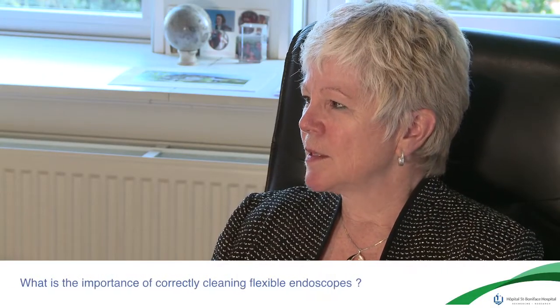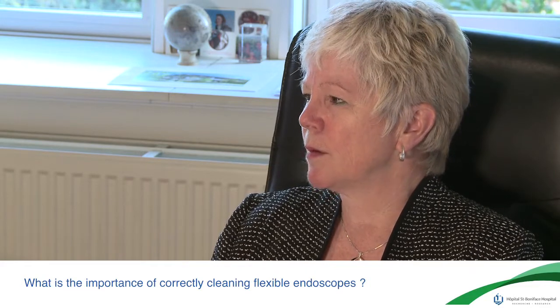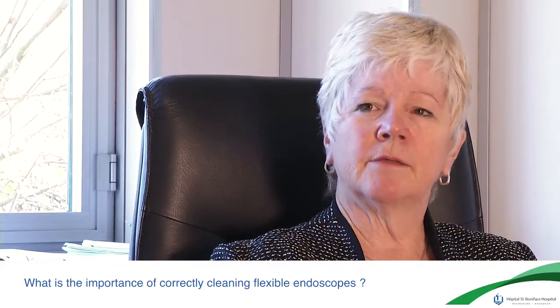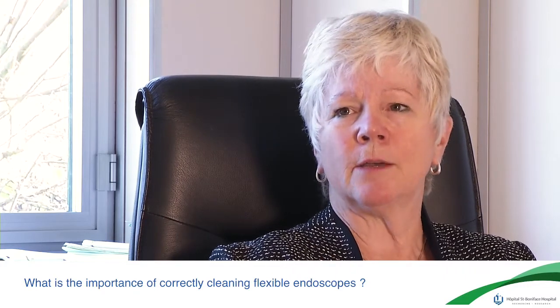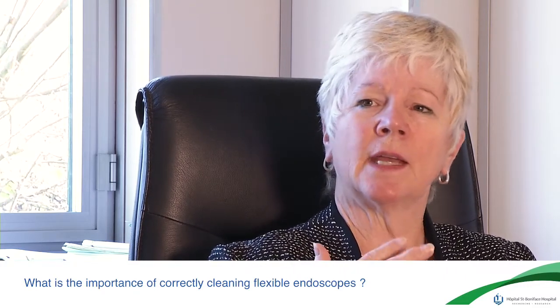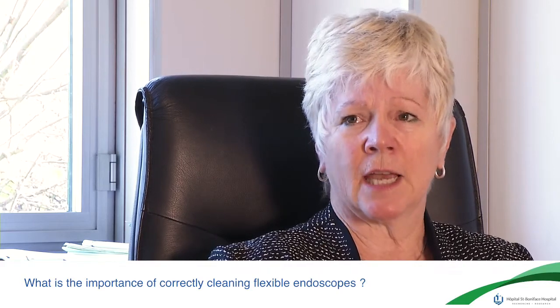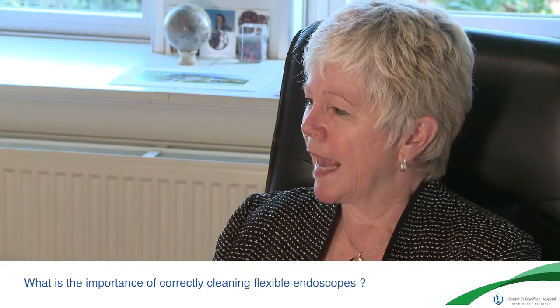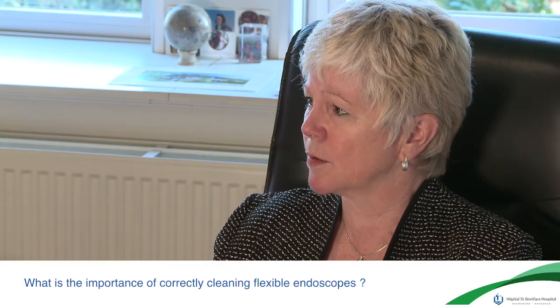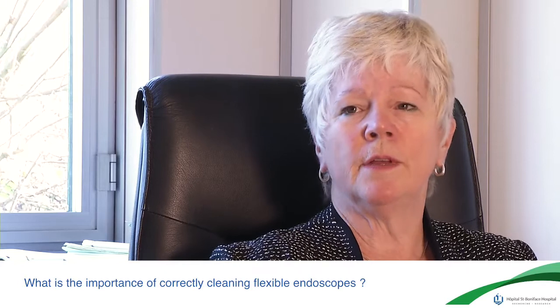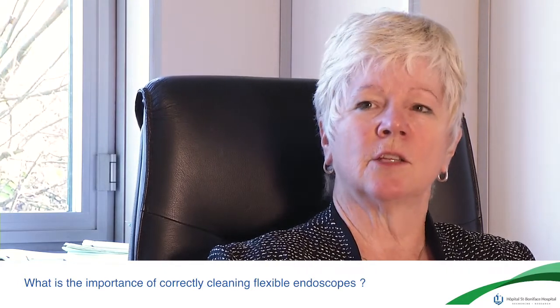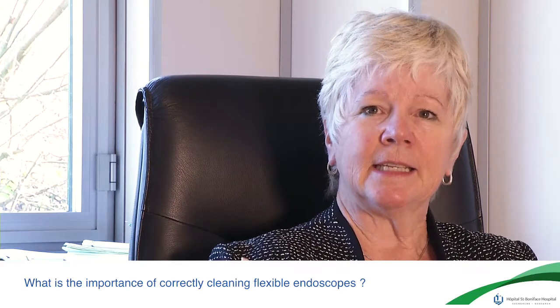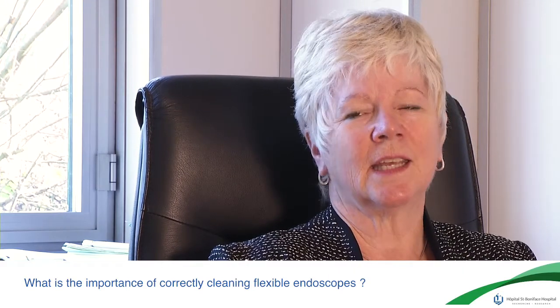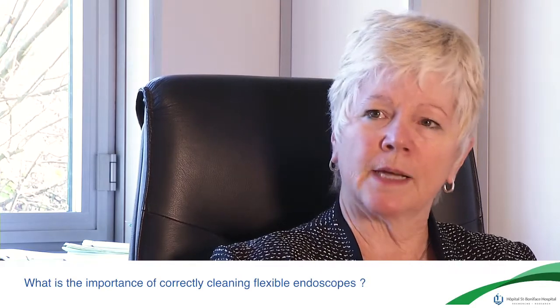What is the importance of correctly cleaning endoscope channels? Correct cleaning of endoscope channels is absolutely paramount, and it requires the use of an appropriate detergent that will effectively remove or solubilize the organic material and the bioburden so that it can be removed with brushing and flushing of the channel. Without adequate cleaning, there can be failure of high-level disinfection, the subsequent step, because if you don't remove enough of the material, it's too much of a challenge for the subsequent high-level disinfection. And if there's failure of high-level disinfection, you can get contaminated scopes and biofilm buildup.